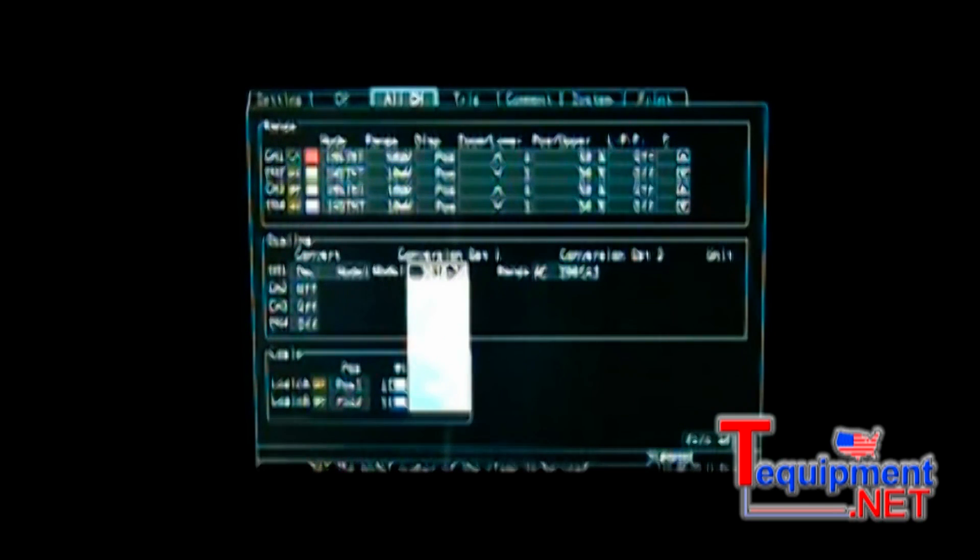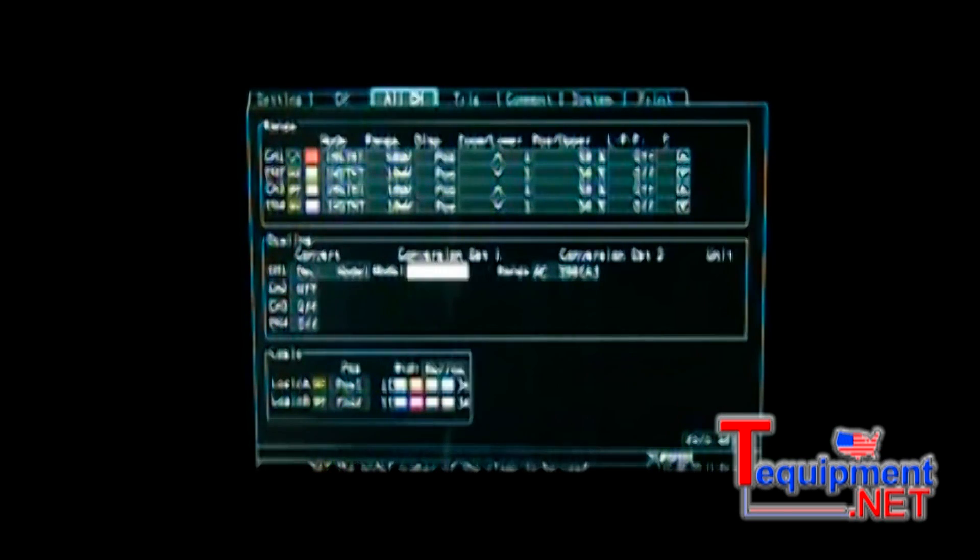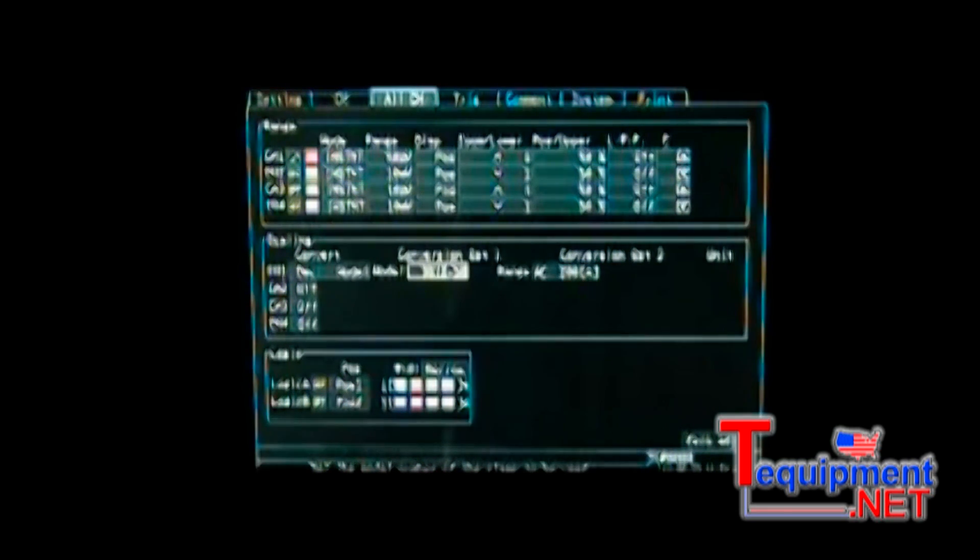The unit can be scaled to show any type of input, whether it be current, pressure or anything that is presented to the recorder as a voltage. The unit even has presets for Hioki current clamps shown in the list to make the scaling as easy as selecting the clamp being used.